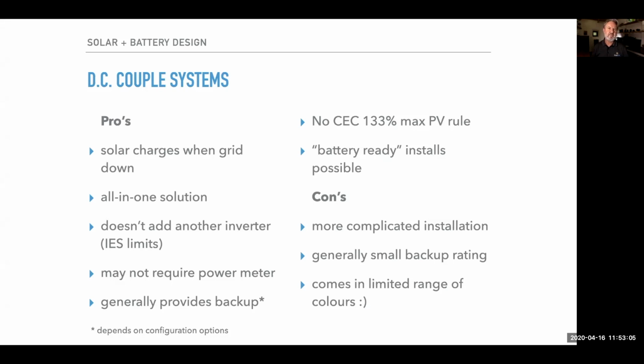Now, most utilities don't enforce this, or they have low limits on it. Well, I shouldn't say they don't care, they do care, but they don't enforce this 5 kVA very vigorously, because it's up to them to choose what those limits are. But we will see that limit drop down. In parts of Australia, it's already at 5 kVA maximum per single phase installation. It's bigger for multi-phase. But if you've got a DC coupled system, you've only got one inverter, so adding solar doesn't increase your IES capacity. You may not require a power meter if you're just directly supplying, via your backup circuit, the loads that you want to support from solar. And DC coupled systems often do have a backup option.